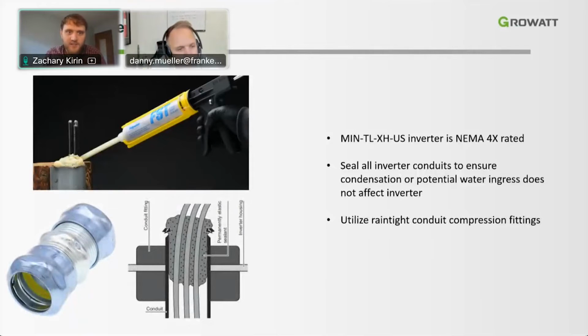Great. This is my personal recommendation to all the installers that will install the inverters. I know multiple inverter manufacturers, in a way to prevent water ingress and air circulating within conduits, will seal the conduit ends for their inverter. They'll seal the conduit ends wherever they're terminated. I would recommend doing this. It is not within our manual that says not to do this.